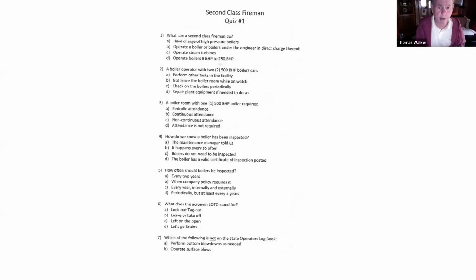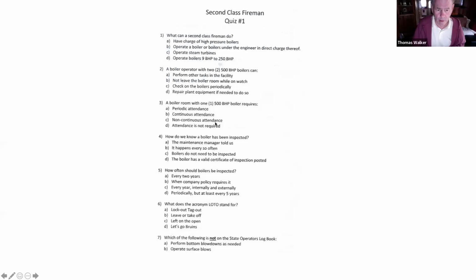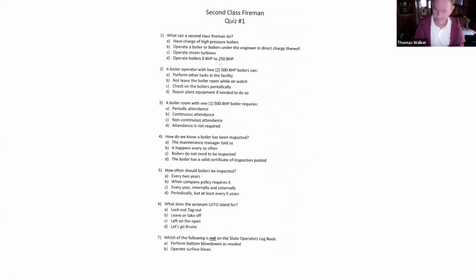How do we know a boiler has been inspected? How about number 3? Number 3: a boiler room with a 500 bhp boiler requires continuous attendance? Nope. It's actually right below the category. It's non-continuous. Remember, non-continuous is 251 to 500. Continuous is 501 and above.